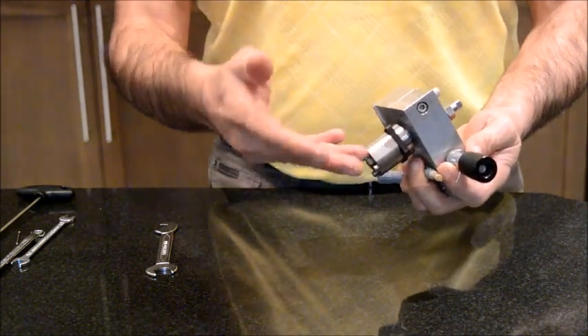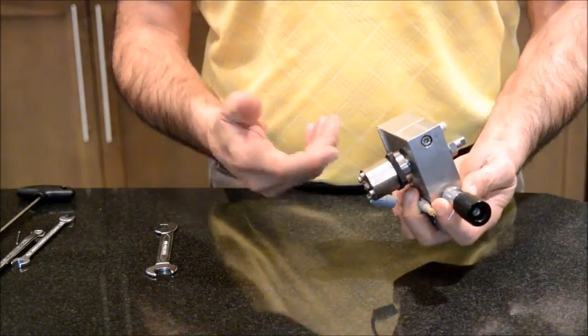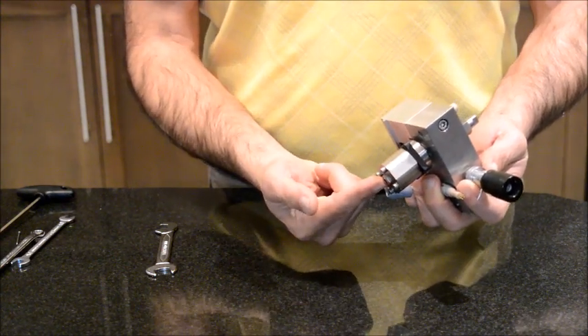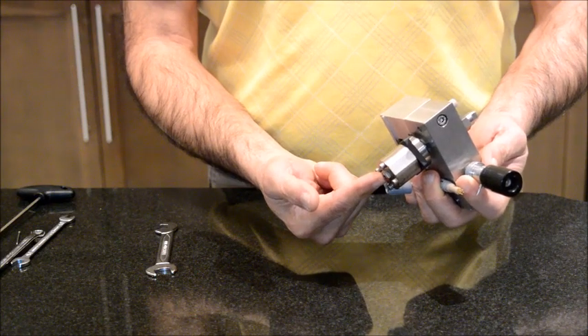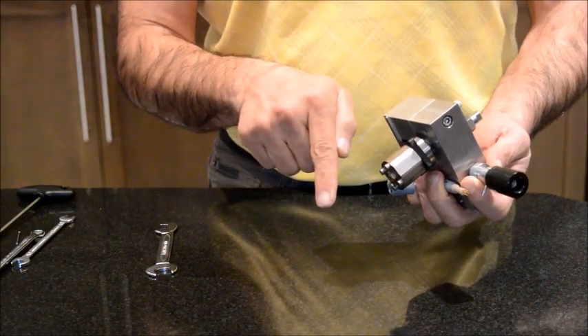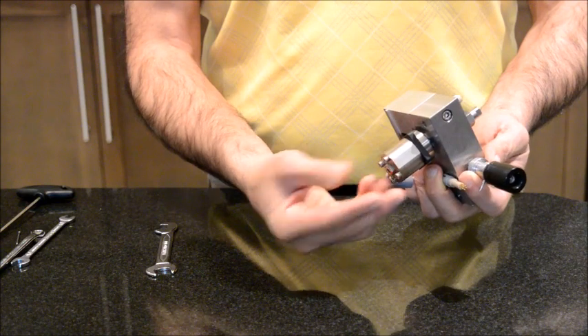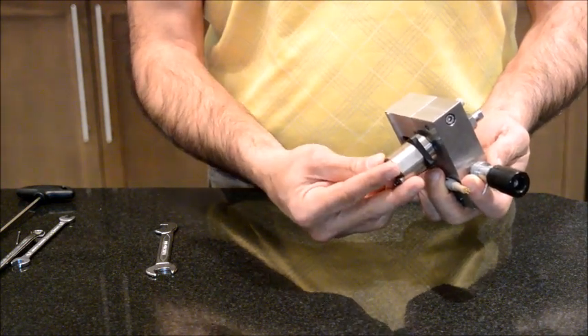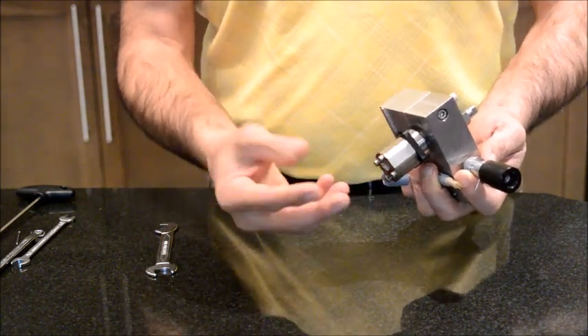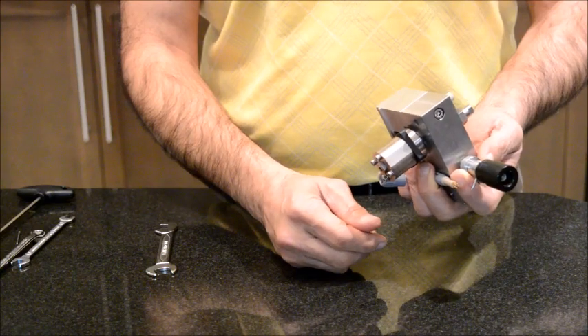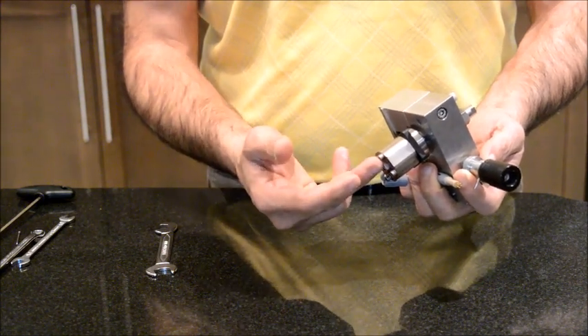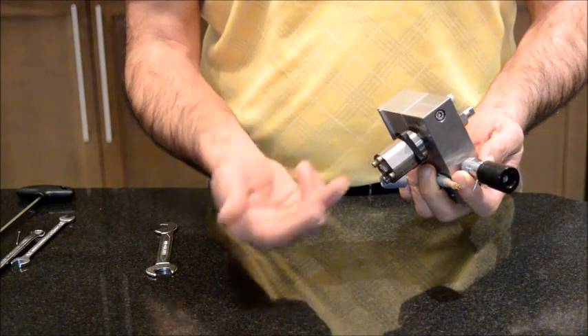This part that you see at the bottom they call it active inlet valve. What it does is that it allows the mobile phase to go to the pump head but prevents it from coming out due to the back pressure. They call it active because this unit is able to remove the air bubbles that is going to the pump. This unit is the standard for all the Agilent HPLC 1100 but for the 1200 and 1260 series this becomes optional so you could buy either active inlet valve or passive inlet valve.